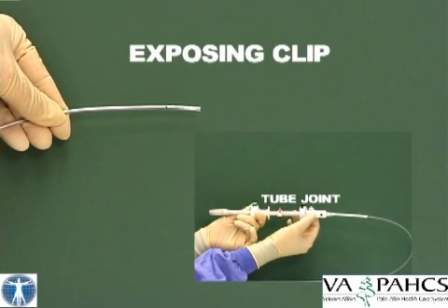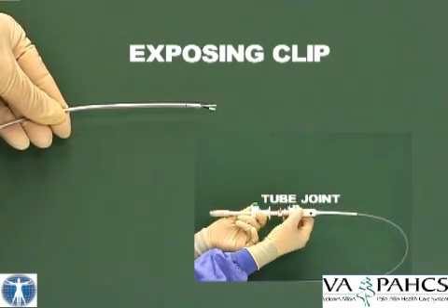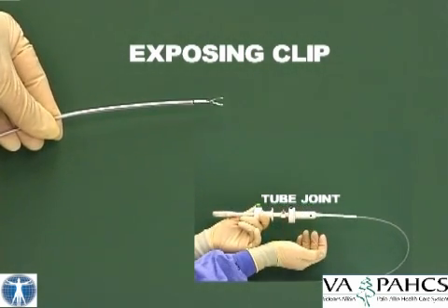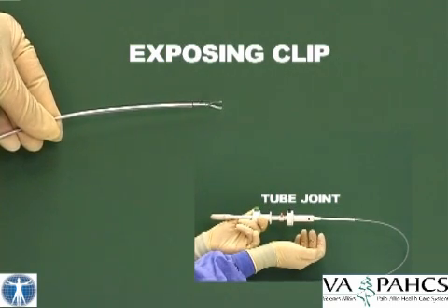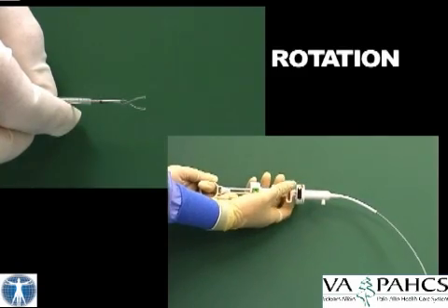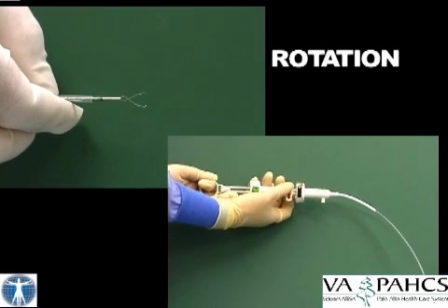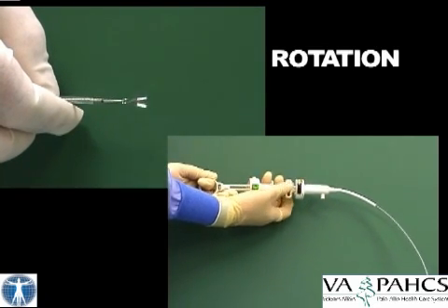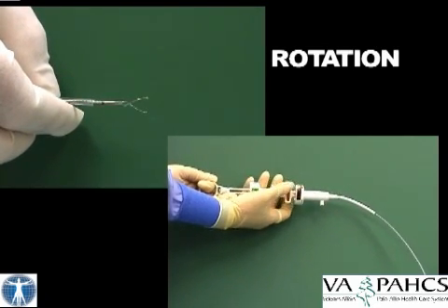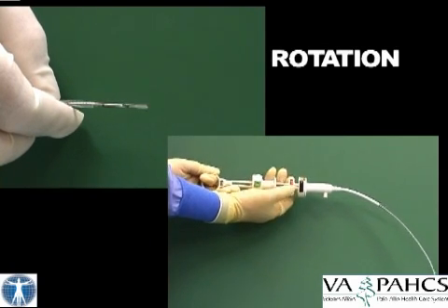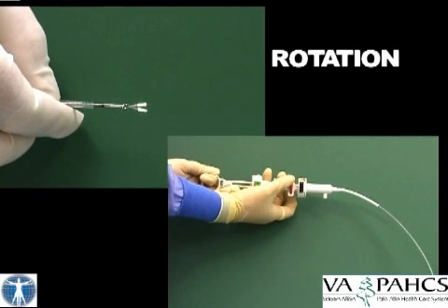Advance the tip of the clip fixing device out of the end of the endoscope. To expose the clip from the tube sheath, pull the tube joint toward the handle ring until it clicks and locks. This does not require depressing the black release button. The clip can then be rotated into a desired position by spinning the red wheel either in a clockwise or counterclockwise fashion. There is a slight delay between the movement at the red wheel and movement of the clip.